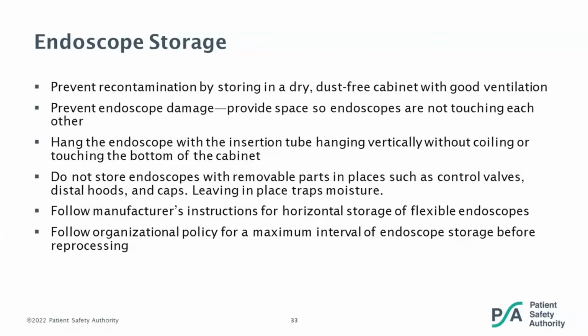Making sure that if you're using an older option, the endoscope is hanging with the insertion tube hanging vertically, without coiling or touching the bottom of that cabinet. And then, not storing the endoscopes with removable parts in place, with the control valves, the distal hoods, caps, etc., because leaving those things in place can trap moisture. You want to follow manufacturer's instructions for that horizontal storage of flexible endoscopes.